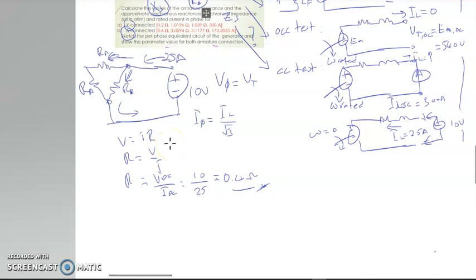So if you are calculating the equivalent R available on the branch, the R that we see from here, the equivalent R or RDC, is equal to VDC divided by IDC. The VDC we apply divided by IDC, so we get the R equivalent or RDC is 0.4 ohm. Meanwhile for RA, you can see here it is a delta connection.